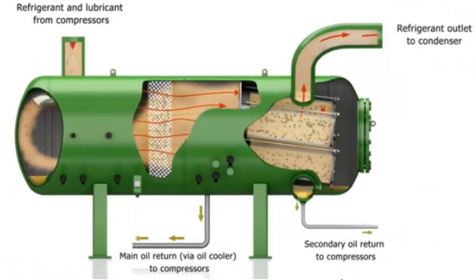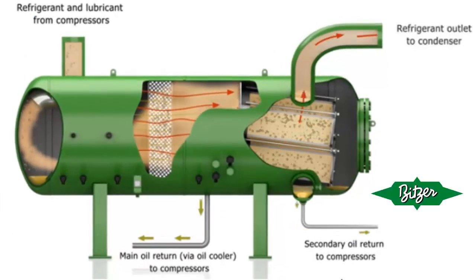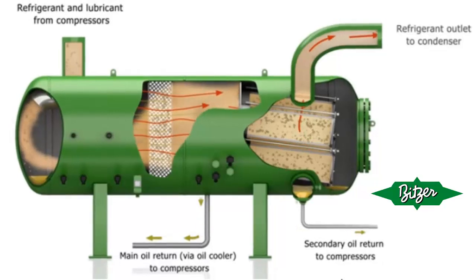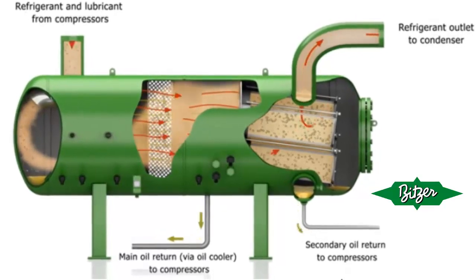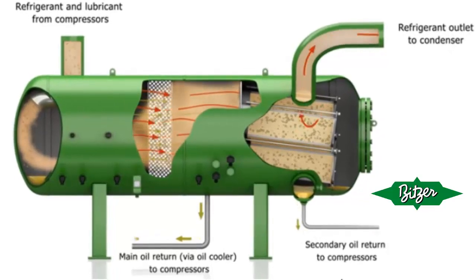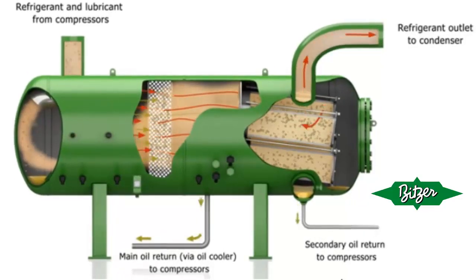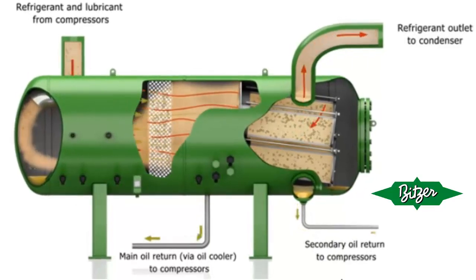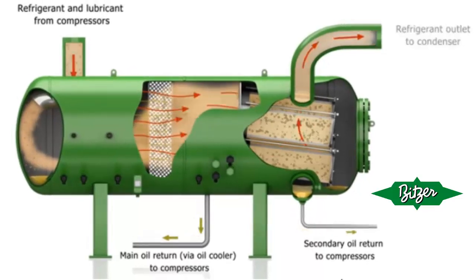Oil Separator. Inside the separator, oil particles undergo a change in direction and a decrease in speed, causing larger oil particles to leave the refrigerant and fall to the bottom of the separator. On the other hand, small oil particles impact the internal fibers of the separator's internal filter, merging into larger oil drops that can then be collected more easily.